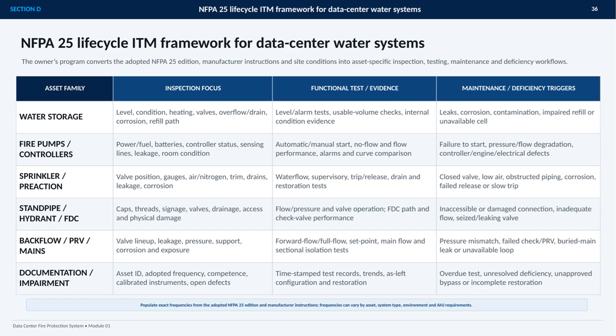Sprinkler and preaction systems focus on valve position, air or nitrogen, water flow, supervisory signals, trip and release performance, and restoration. The same logic applies to standpipes, hydrants, FDCs, backflow devices, pressure-reducing valves, and water mains. Inspect the physical condition, perform flow or pressure tests, and identify failures such as inaccessible connections, pressure mismatch, leaks, or unavailable loops. Finally, documentation must capture asset IDs, calibrated instruments, timestamp results, trends, open defects, and restoration status. Exact frequencies must come from the adopted edition, manufacturer guidance, system type, environment, and AHJ requirements.